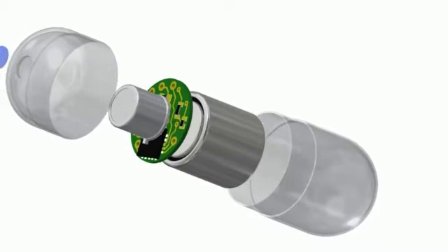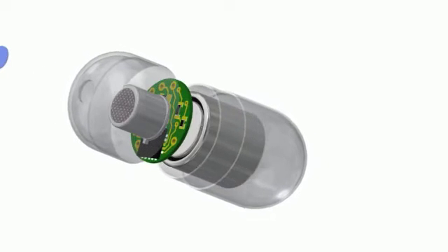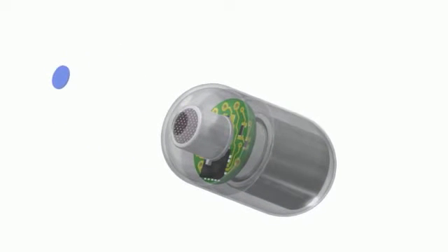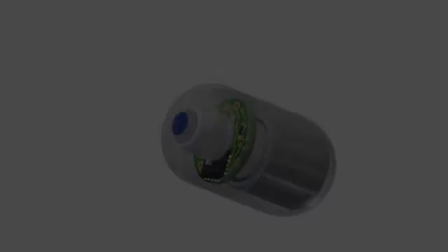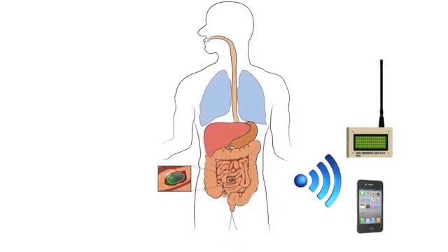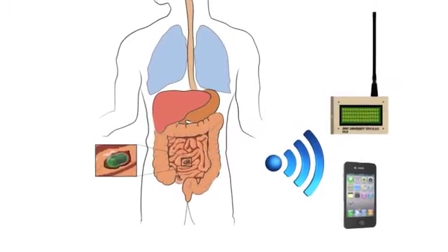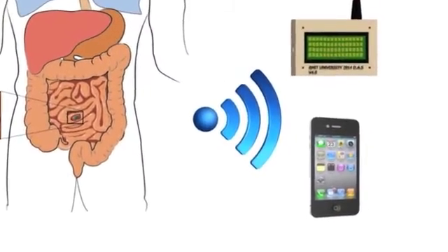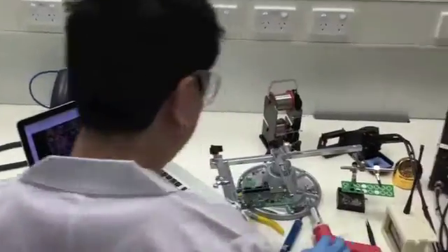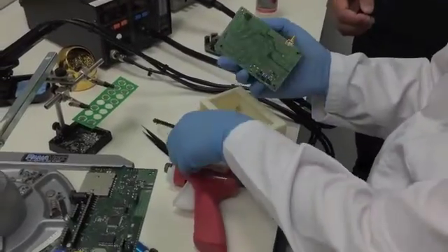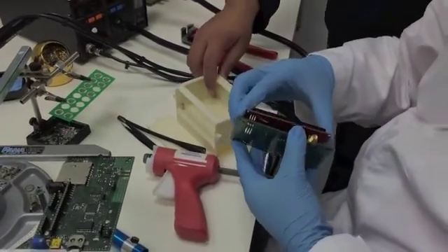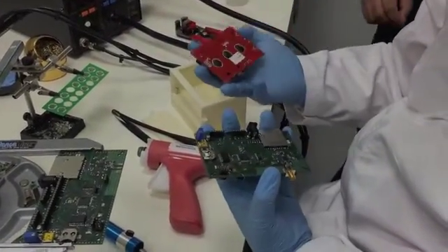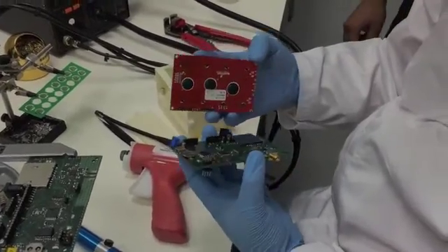Within its small 12x35mm housing, the capsule contains a high-capacity, non-hazardous power supply, a microcontroller and a wireless transmitter operating at 433MHz and a spiral antenna. These elements obtain, convert and process gas sensor outputs and subsequently communicate the data to a light handheld external receiver. The gas data is sent out every 5 minutes and between transmissions, the system goes into sleep mode to increase battery lifetime.